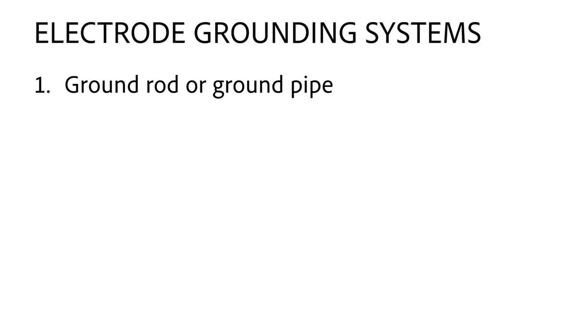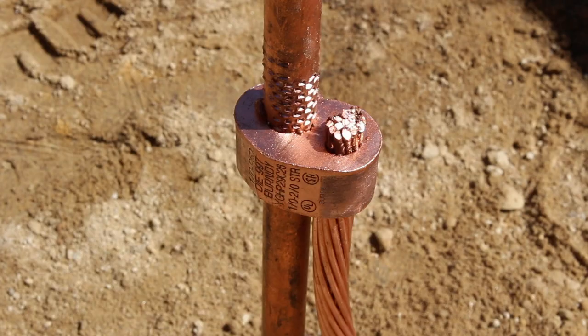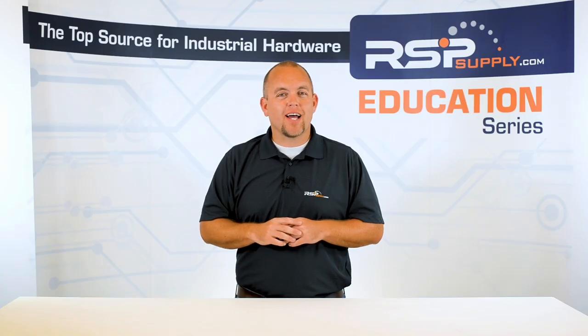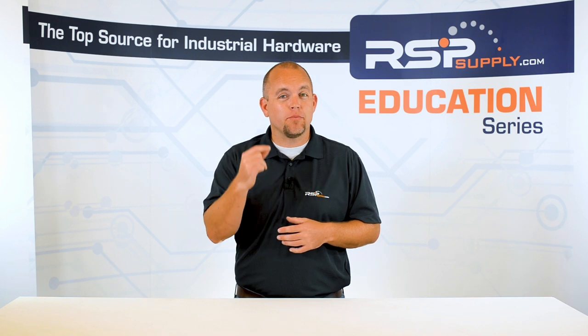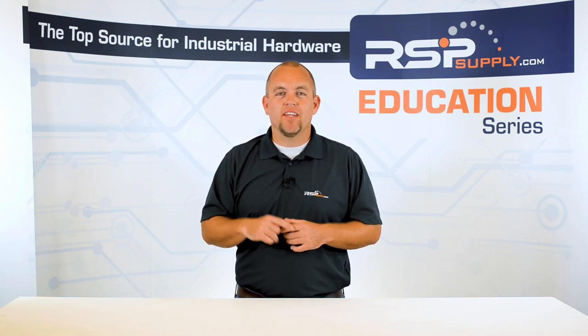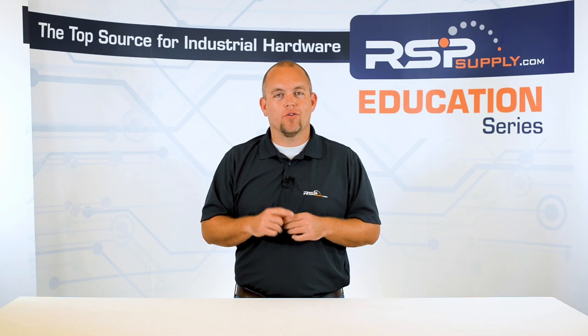First, and probably the most common electrode grounding system, is the ground rod or ground pipe. This rod is to be no less than eight feet in length and should come in direct contact with the soil. The more conductive the rod or pipe is, the better your grounding system will perform. There are many different types of grounding rods and installation methods because of the effectiveness and popularity of this grounding electrode system.